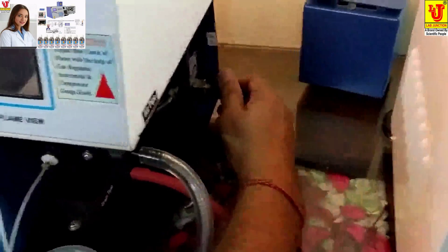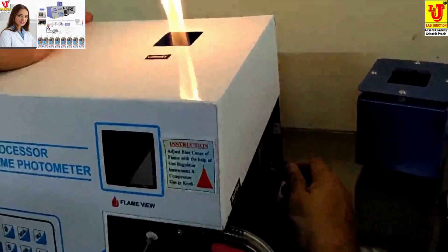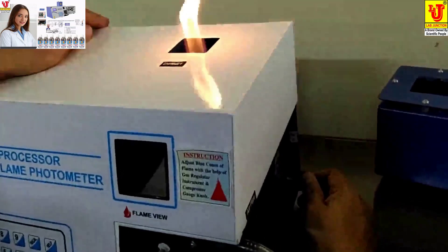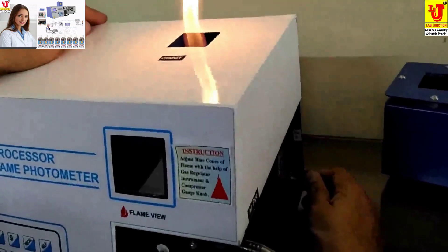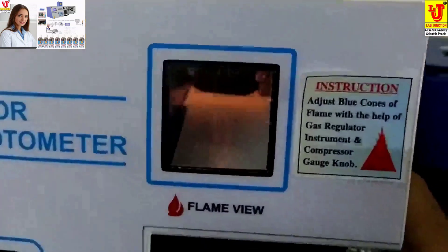Now we have to adjust the flame for the flame photometer — slowly minimize the gas regulator. Take the view from that opening to observe the flame.